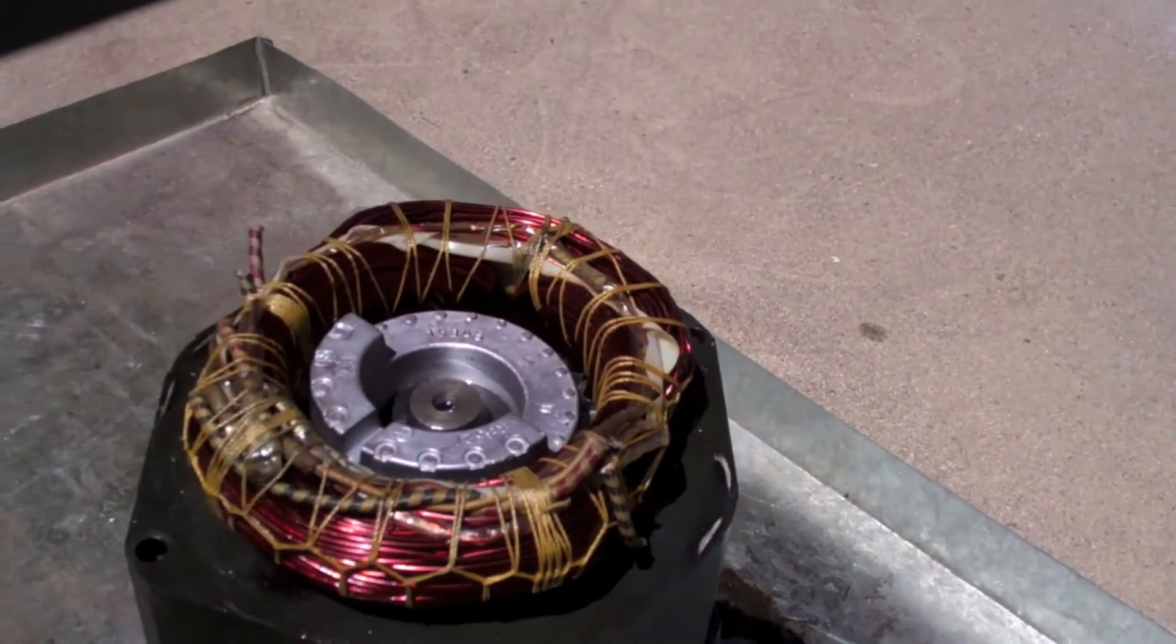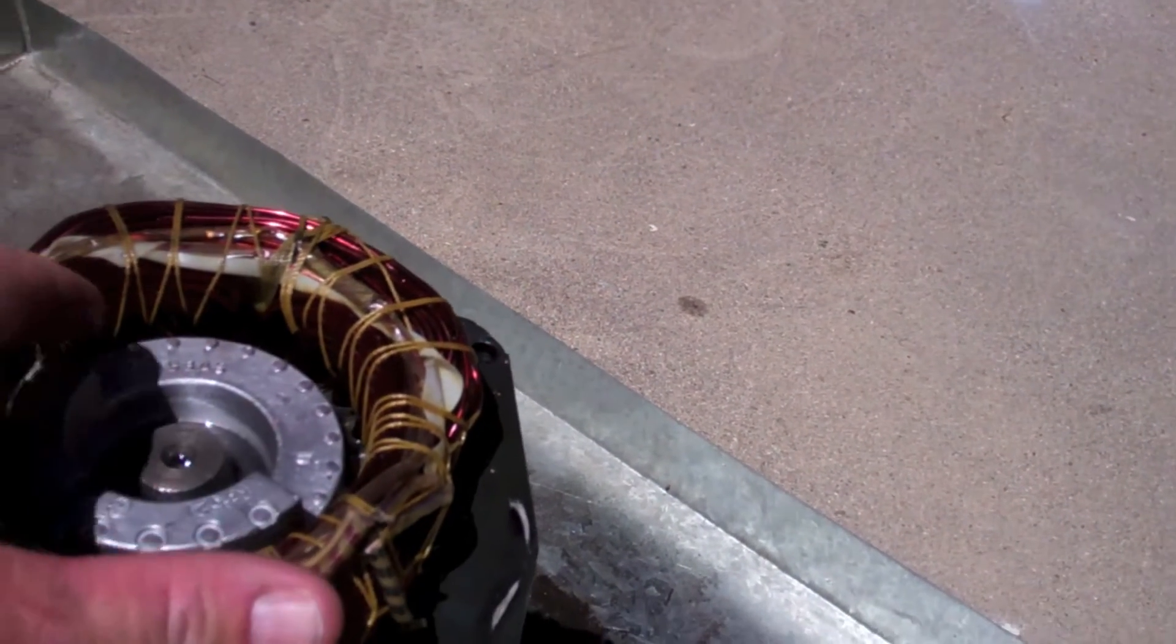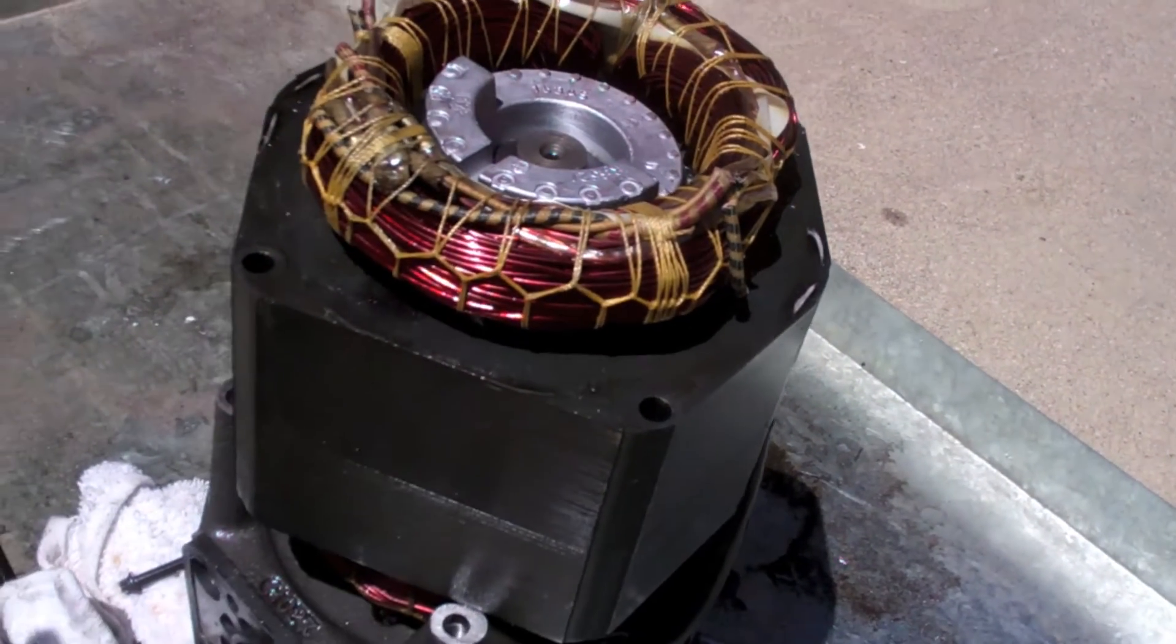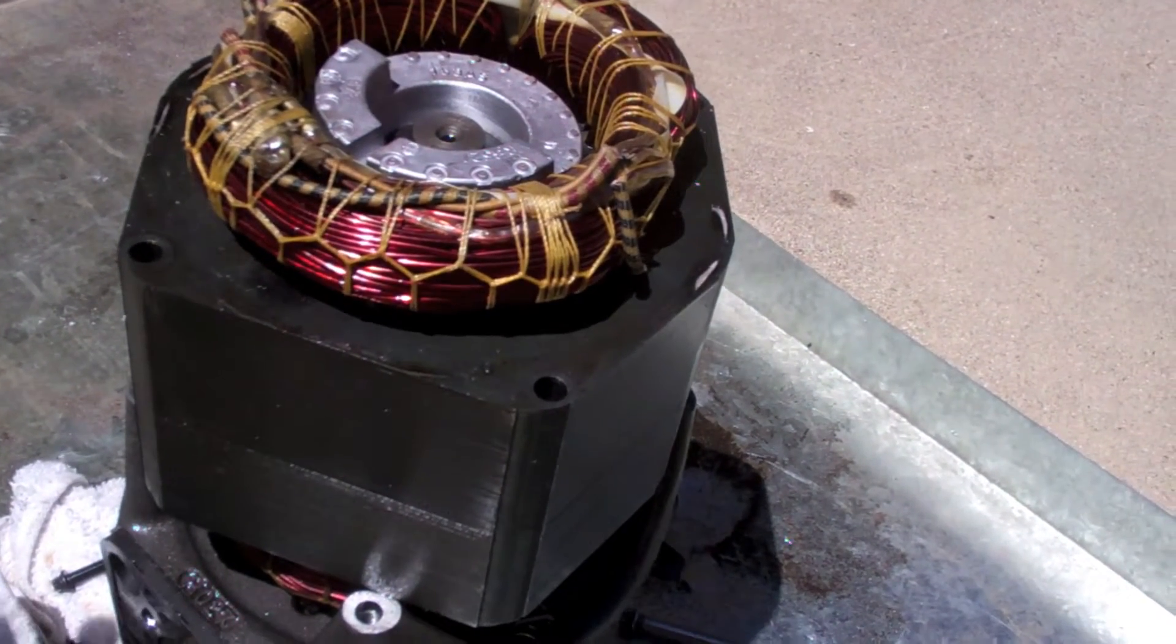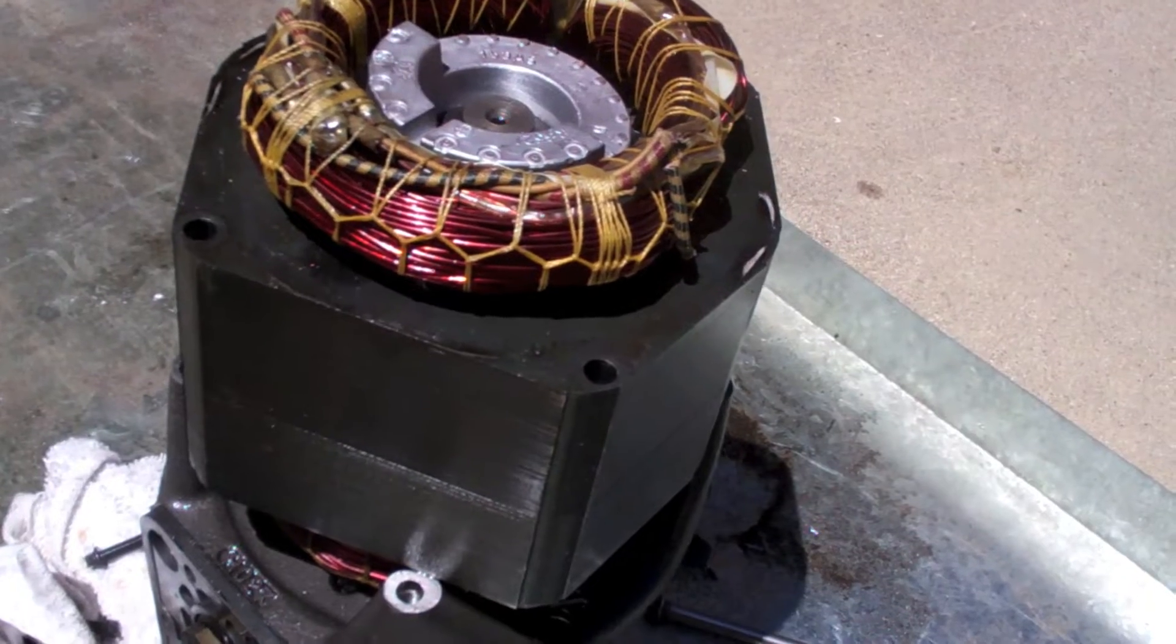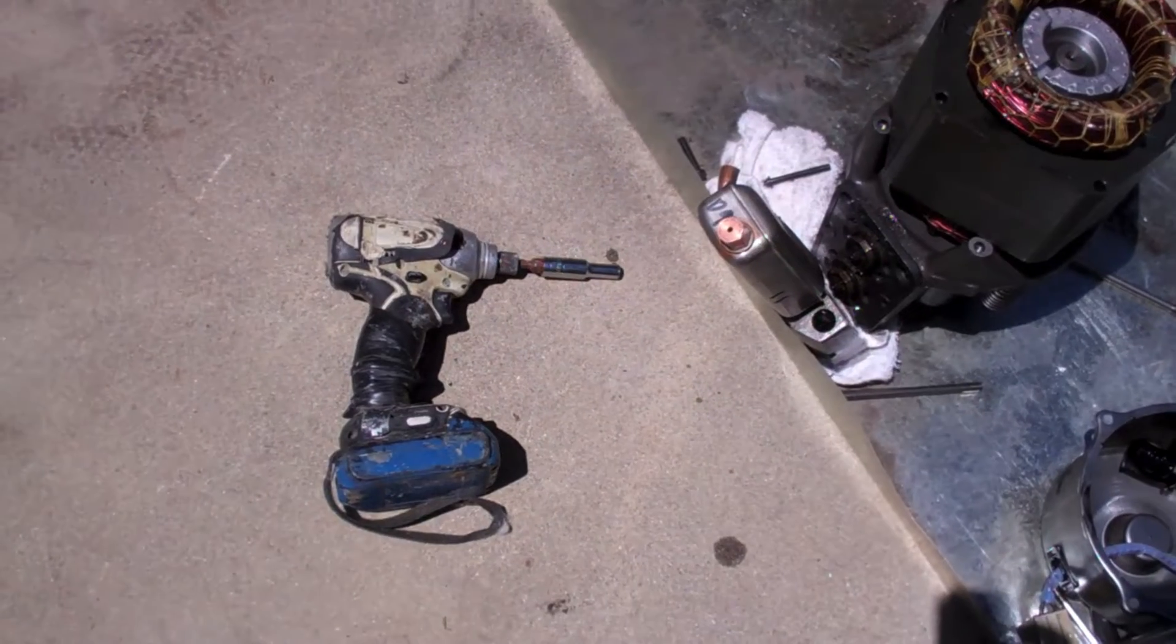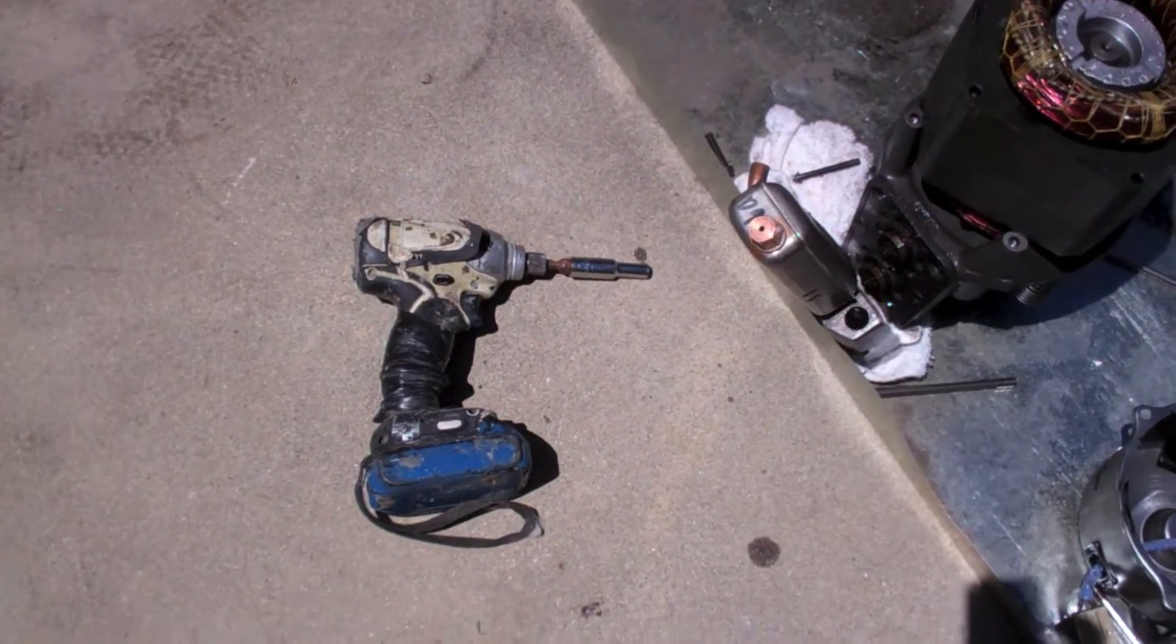But this motor here is definitely, it was diagnosed right, it's locked. I think it's got a lot of liquid, so I still got to do some tear down on this and see what happened. I got old trusty helping out right now, yellow Makita, still working.